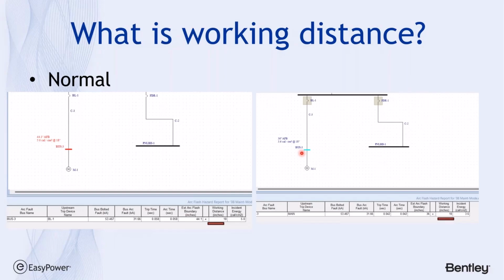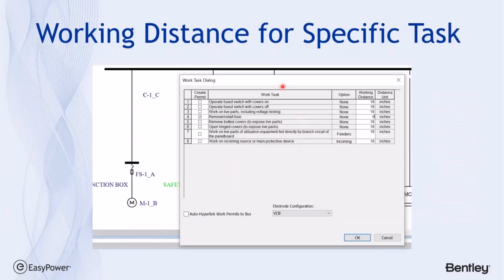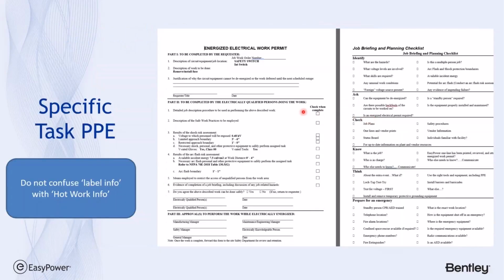it doesn't amount to the correct calculations for the task or the work that's going to be done. And that's why EasyPower will create the work permit, and based upon the task that's selected, I can modify or show what the working distance is that my body or parts of my body will be in contact with or in the vicinity of. And so when EasyPower prints out the results for that work permit, that information will be shared, not only the study and the typical arc boundary for cover removal, but also the working distance for this particular task and the PPE ratings that we need to have when doing that work.